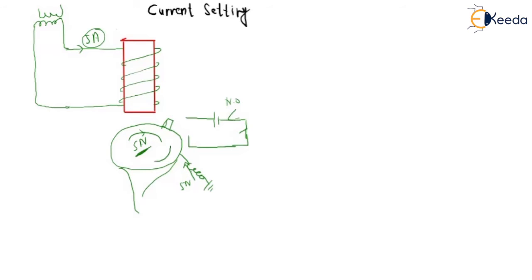So now 5 Newton force has been applied in this direction and 5 Newton has been applied in the restoring direction. Now if you want to change the I pickup, we know that the MMF will always be constant. If you do not want to change the time, it means torque should be constant. Torque means the flux should be constant, and flux means the MMF of the core would be constant, meaning N1 of I pickup 1 is equal to N2 of I pickup 2.